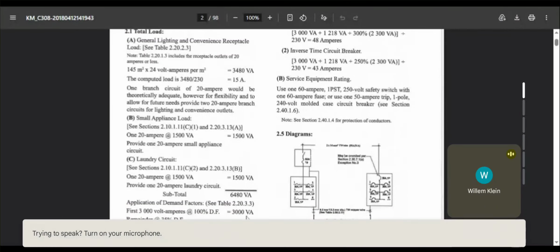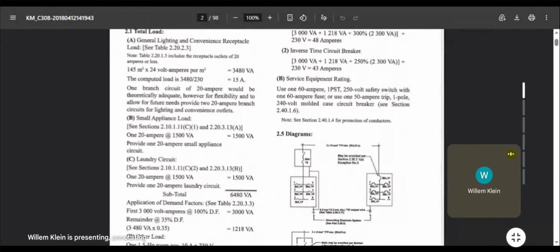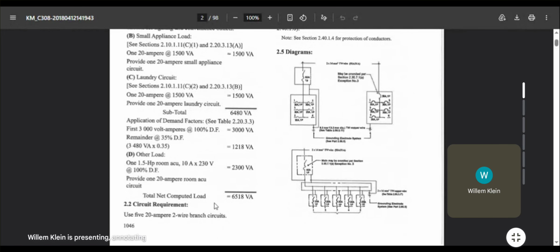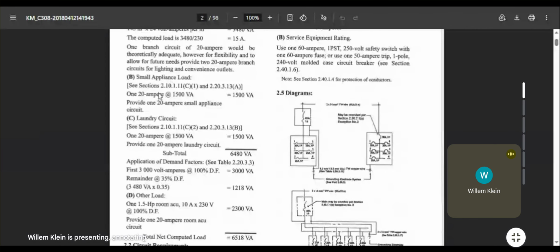When there is an exceeding load, no more than 3000 volt-ampere, you will use the corresponding demand factors. Okay? So like for example in this one, that is for your lighting and small appliance, including laundry circuit. Those are included in your different branch circuits, and then you'll get the total VA of those circuits, and then you will apply the demand factor if your initial computed total load for your non-continuous loads will exceed 3000 VA. Okay?